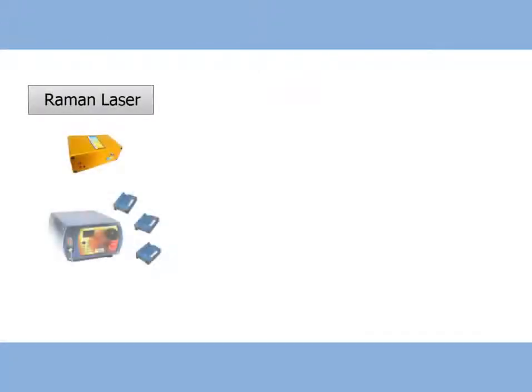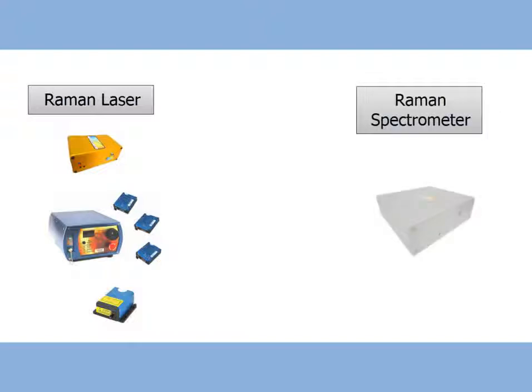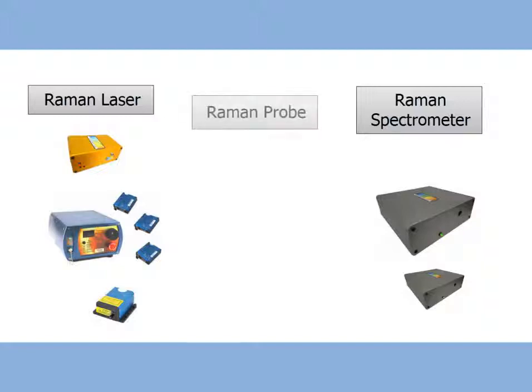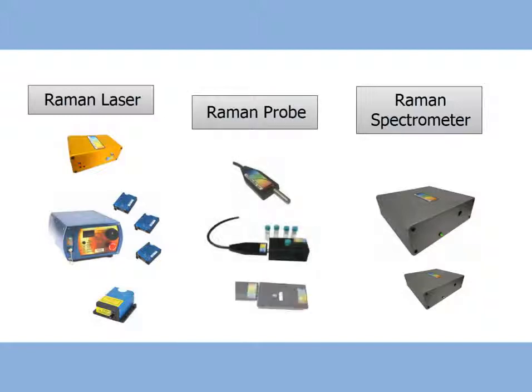A Raman Spectrometer system consists of a Raman laser generally characterized for high output power and sharp line width, a Raman Spectrometer which is configured for high resolution and high sensitivity simultaneously, and a Raman probe which delivers the laser light to the sample and returns the scattered light back to the spectrometer.